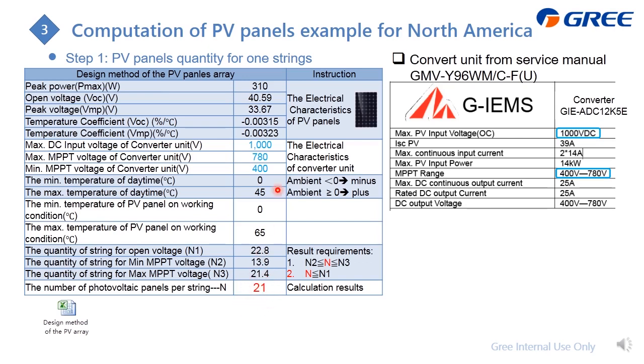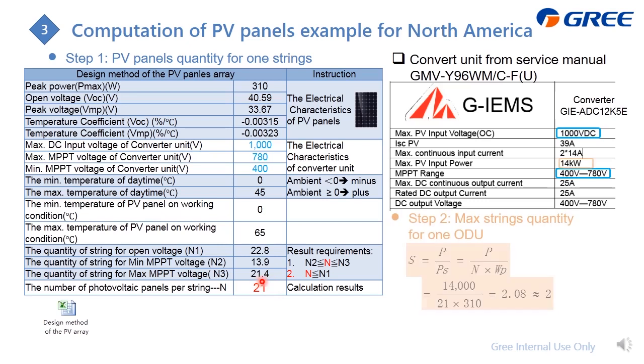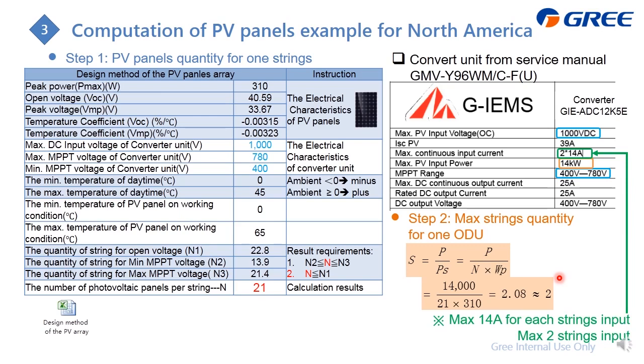So if this is correct, you can get 21 pieces of the PV panels for one string. And how many strings? You can get the P from here, it is 14 kilowatt. So finally we can get max 2 strings. And as for this one, it is the max 14 ampere for each string. This is for you to do a double check.